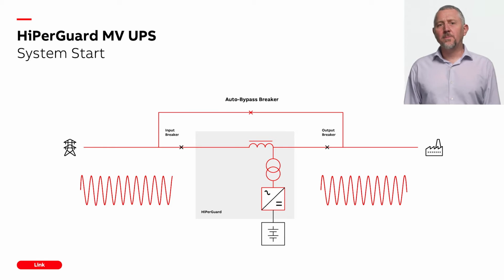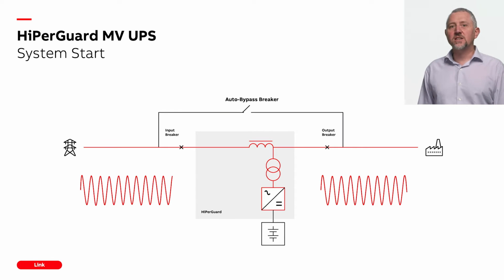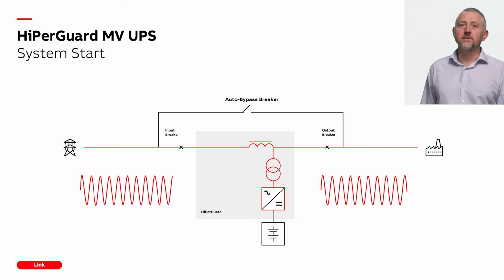Finally, the auto bypass breaker opens, directing the current through the HiPerGuard MV UPS. Initially, the phase shift between input and output being 0, gradually adjusting this phase shift to 30 degrees, with the start process now complete and the unit now operating in power conditioning mode. This whole process takes less than 1 second with full load.